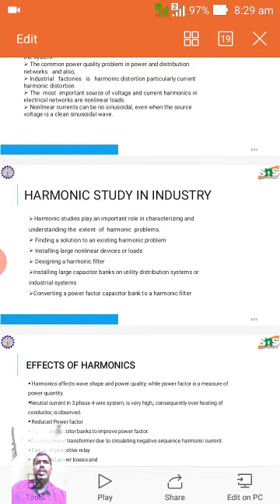Therefore, the harmonic sources can be classified into two major groups. First one, commercial and industrial loads. Commercial facilities such as office complexes, departmental stores, hospitals, universities, and internet data centers are dominated with high efficiency fluorescent lighting with electronic ballasts, adjustable speed drives for heating, ventilation, and air conditioning loads, elevator drives, and sensitive electronic equipment supplied by single phase switch mode power supplies. Besides, modern industrial facilities are characterized by the widespread application of nonlinear loads. These loads can make up a significant portion of the total facility loads and inject harmonic current in power systems.